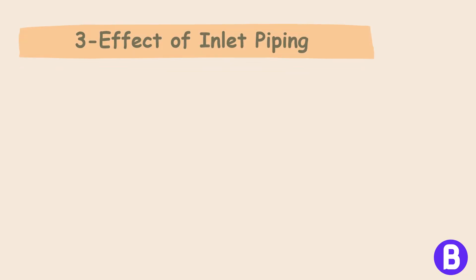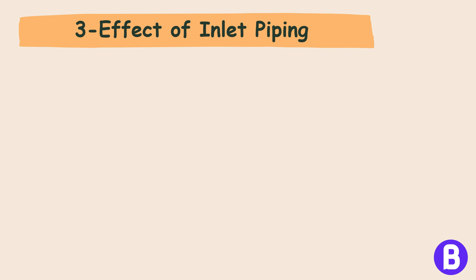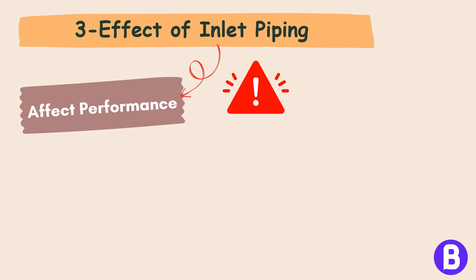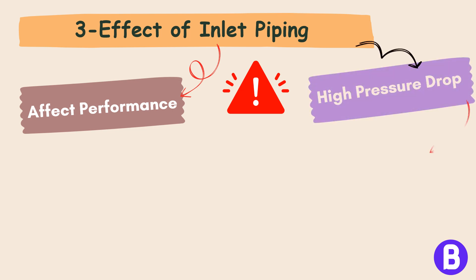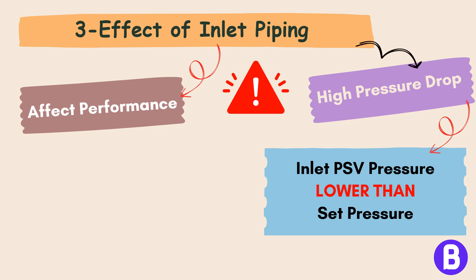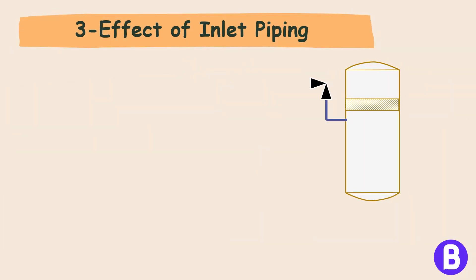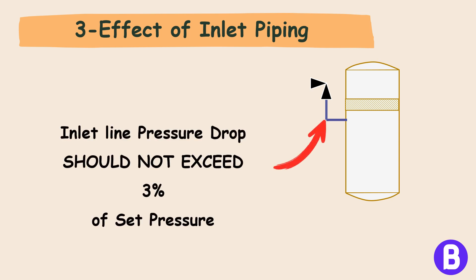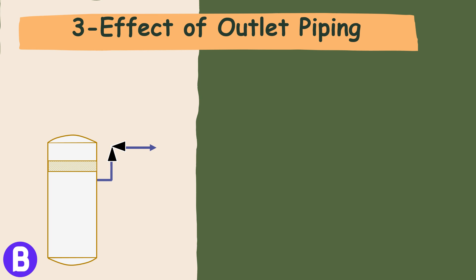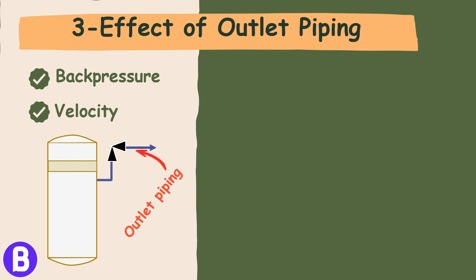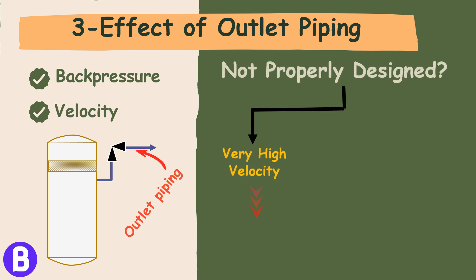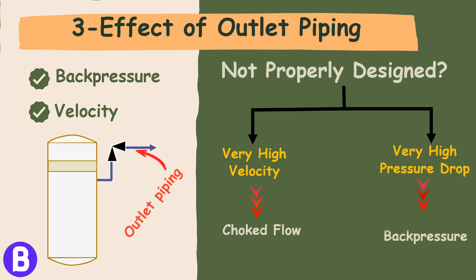Factor 3: Effect of Inlet and Outlet Piping. Inlet and outlet piping configurations significantly impact PSV performance. A high pressure drop in the inlet piping would lead the PSV to sense a lower pressure than the actual pressure, causing PSV chattering and interference with the PSV blowdown characteristics. To prevent this, it is critical to ensure that the pressure drop in the inlet line does not exceed 3% of the PSV's set pressure. Conversely, for outlet lines, a very high velocity can lead to choked flow, while a very high pressure drop shall cause high backpressure on the PSV, both affecting the PSV's ability to relieve pressure effectively and potentially leading to unstable valve operation.